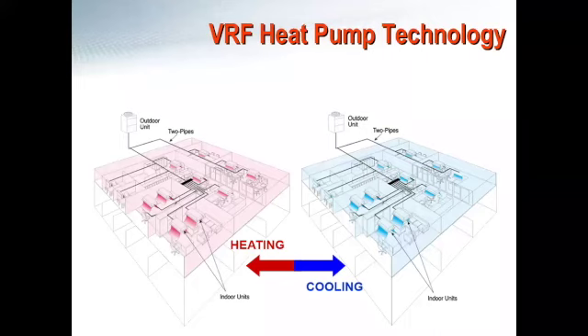So this is a very common type of VRF technology. This was actually the first type introduced in the United States on a commercial level. This is great if you're working on somewhere that's going to have a very matched load profile. You're not going to see a lot of diversity in the space. This is good for schools or any kind of institutional building where they're used to that kind of 2-pipe changeover into heating or cooling. Luckily, with VRF, you're able to be significantly more accommodating than that 2-pipe hydronic, but it's very similar in the way it's going to change over.